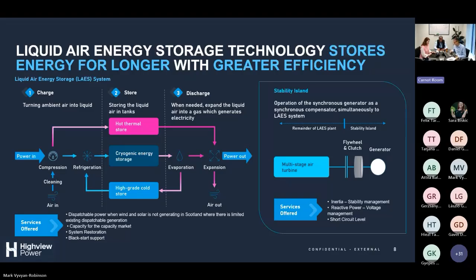The hot store is in the form of molten salts - that's the technology we're using. On the right-hand side, we put a clutch between the generator and the rest of the plant, and we also add a flywheel. This means the generator and flywheel can act as a stability island, providing grid services to the system operator 24/7, irrespective of what's happening in the rest of the plant. This synchronous generation is really needed in the UK, and a very important part of our needs case.